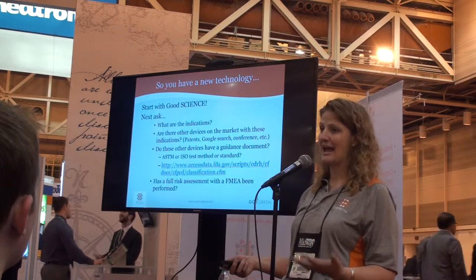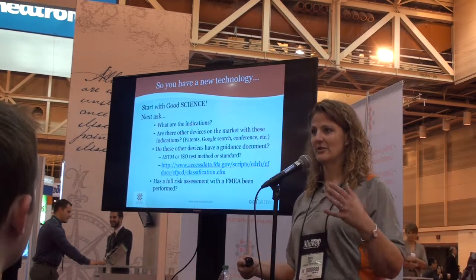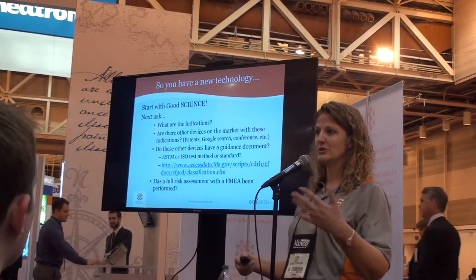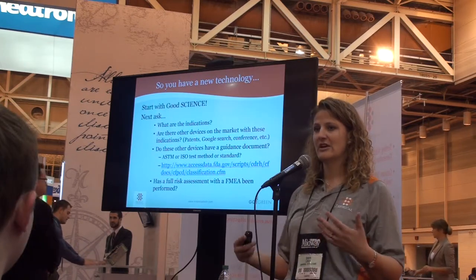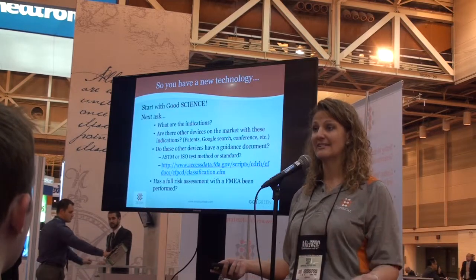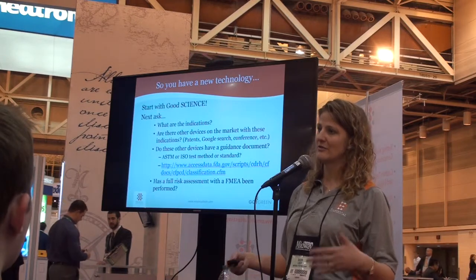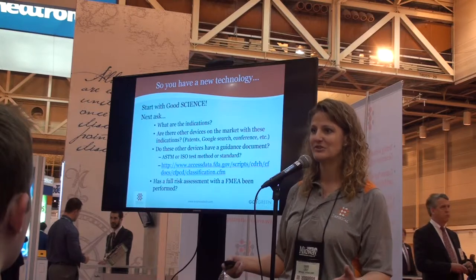Your predicate may not have that feature, so it's up to us to determine if that device or feature is safe. That will come out of your FMEA. You'll go through your FMEA exercise, and if there's something of concern, we'll devise a custom protocol and test to characterize it, relate it to research and published literature, and make sure that it's safe. In those cases, you don't have to have a predicate device that tests against that feature, but you need to make sure that feature is safe.